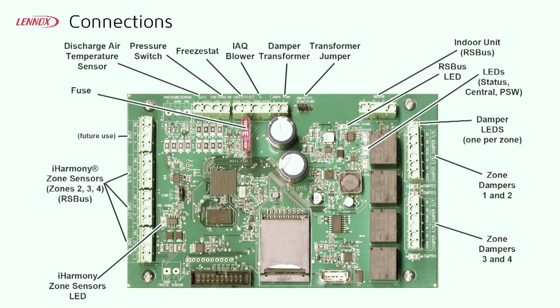But it should be reversed, because on a 3-wire, that NC terminal is counting on it being normally closed, and so it's going to put 24 volts there when it wants to open the damper. So if you've got a 3-wire setup, you put your open command on NC and your close on NO. Just one of those little quirks of installation.